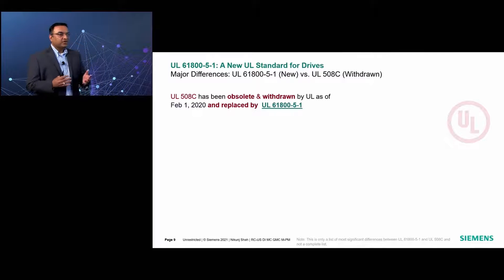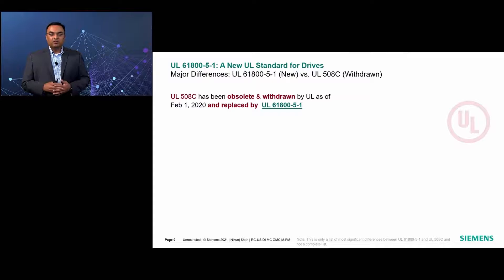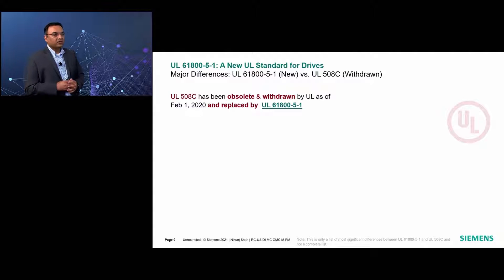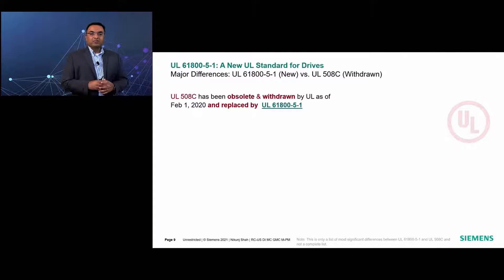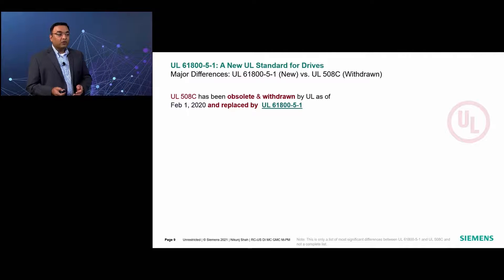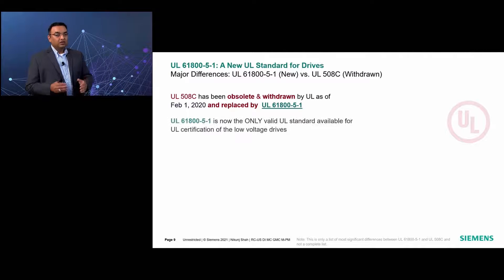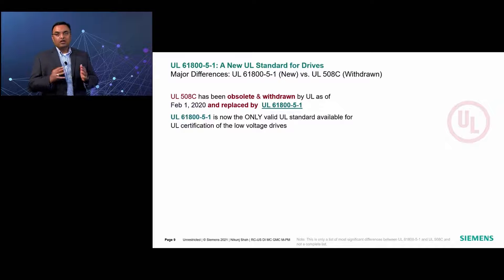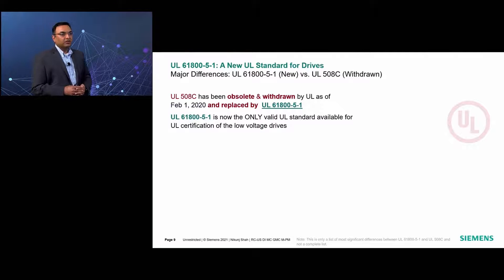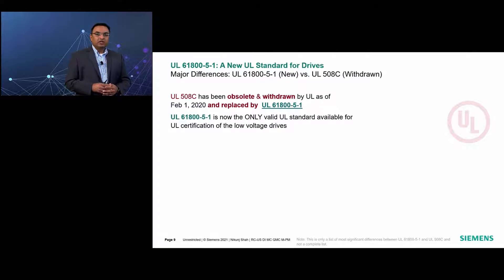The first major difference is that UL508C, which was withdrawn and obsolete last year, was actually an old standard for the low-voltage drives, and it has been replaced with 61800-5-1. Therefore, currently there is only one UL standard available for the safety certification of the low-voltage drive, and that is 61800-5-1.